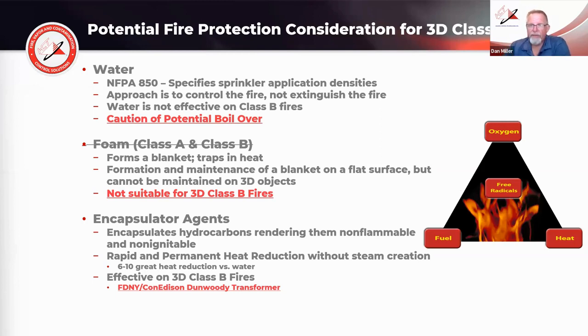We'll talk about it in a little bit, but FDNY worked with Con Edison and Hazard Control Technologies to do some transformer fire protection, as well as just electrical fire protection up to 345,000 volts at a substation. And F500 was successfully utilized in that situation without return current to the nozzle, as long as the standoff distances were observed and a broken stream was used.